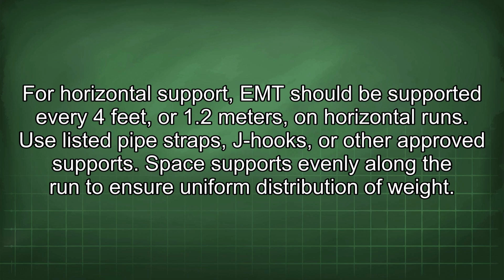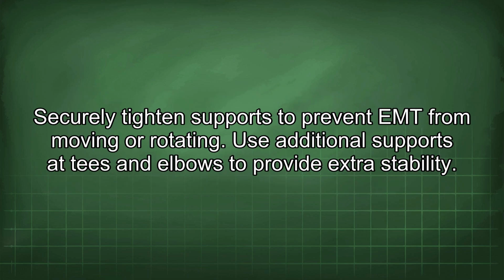For horizontal support, EMT should be supported every 4 feet, or 1.2 meters, on horizontal runs. Use listed pipe straps, J-hooks, or other approved supports. Space supports evenly along the run to ensure uniform distribution of weight. Securely tighten supports to prevent EMT from moving or rotating. Use additional supports at T's and elbows to provide extra stability.